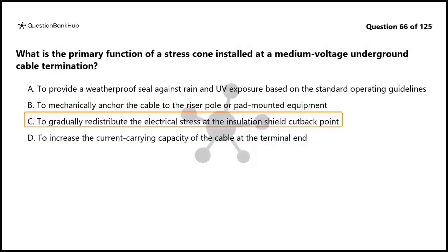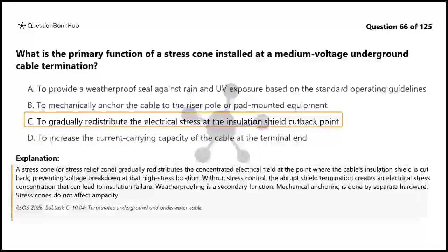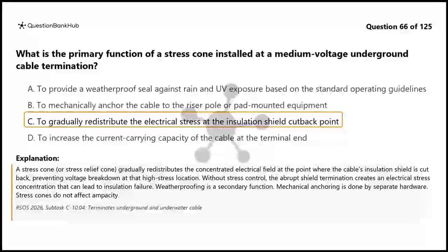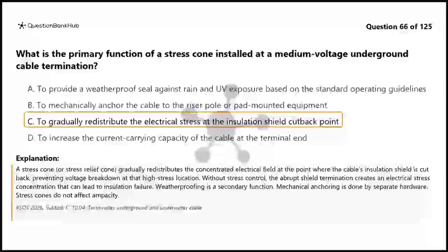The correct answer is C. A stress cone, or stress relief cone, gradually redistributes the concentrated electrical field at the point where the cable's insulation shield is cut back, preventing voltage breakdown at that high-stress location. Without stress control, the abrupt shield termination creates an electrical stress concentration that can lead to insulation failure.